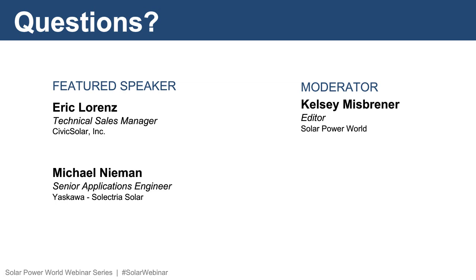All right, thank you. The next question is, why did they choose to make the amount of time longer for the voltage to drop? What I think you're referring to is the rapid shutdown requirement, changing from 10 seconds to 30 seconds. The 2014 rapid shutdown requirement, as it was being compiled, the need for a grid ride-through was not considered, or it was overlooked. Many utilities, though, require at least a 20-second ride-through to allow for any type of utility disturbances.